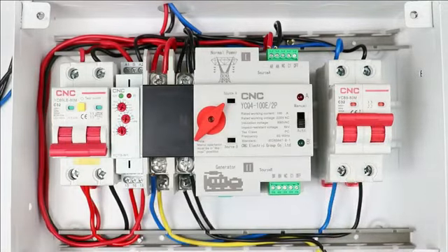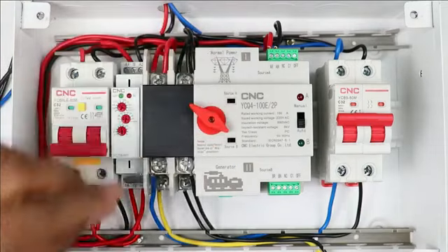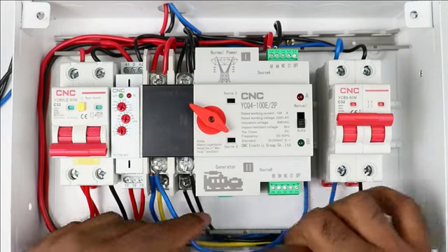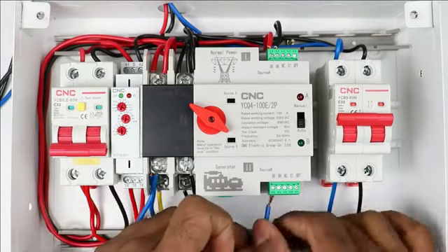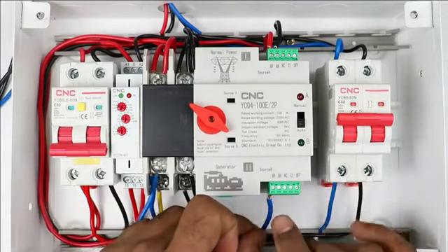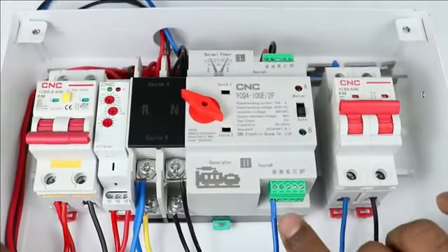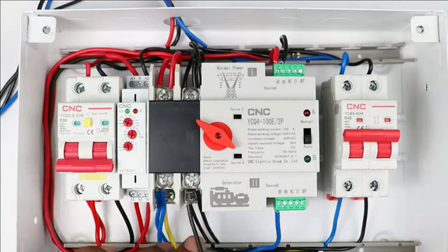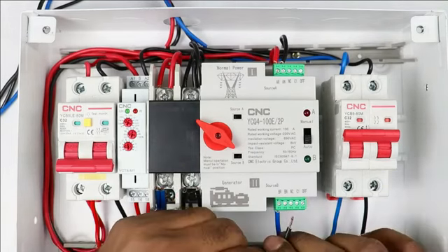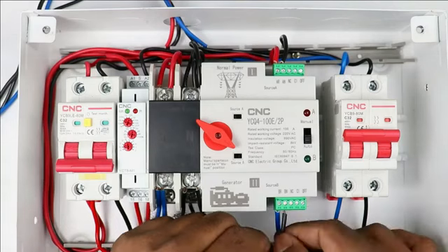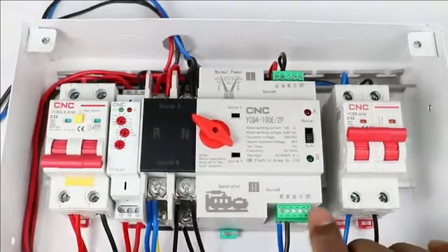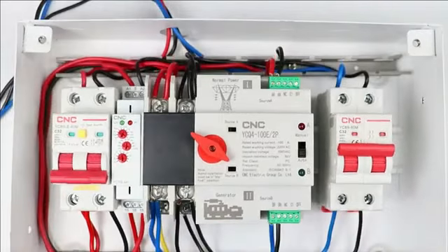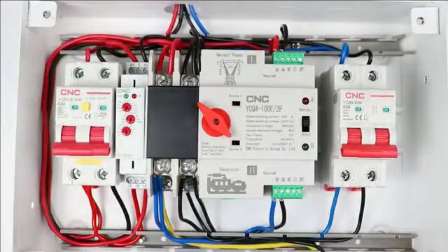through the generator. If you want this changeover directly, then what you have to do is connect a wire with the phase terminal of source B. The other end of the wire is to be connected at the phase terminal of the control terminal of source B. You can see I connected this wire with this terminal. Connect one more wire with the neutral point of source B and connect the other end of the wire with the neutral terminal of the control terminal. We provided the feedback of phase supply and neutral supply at this control terminal. The control wiring of this ATS is now completed.